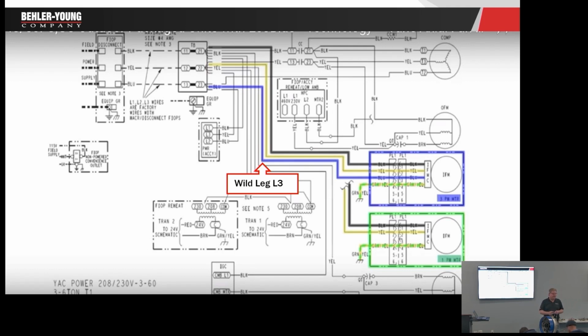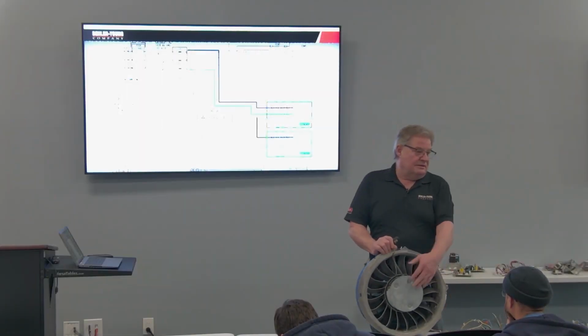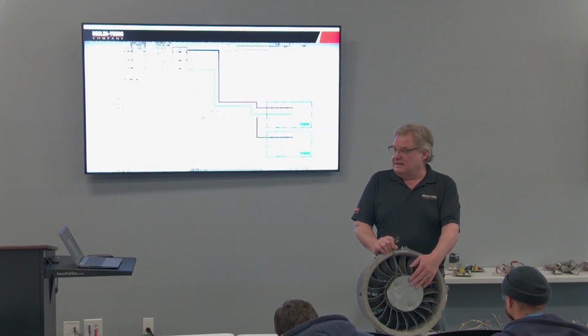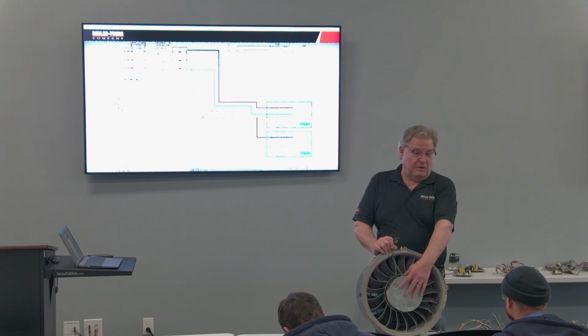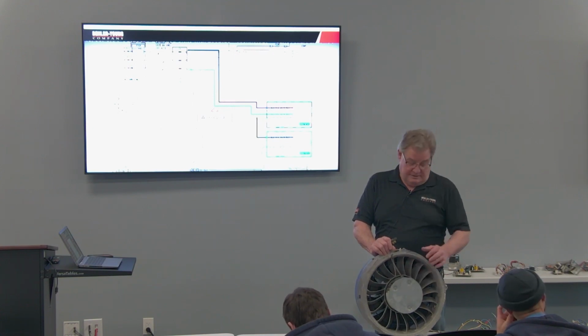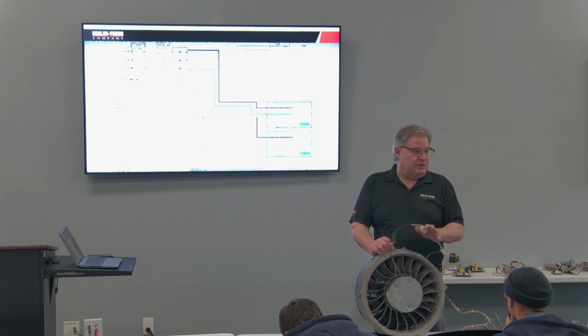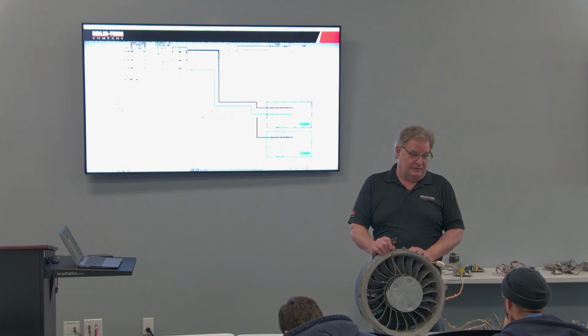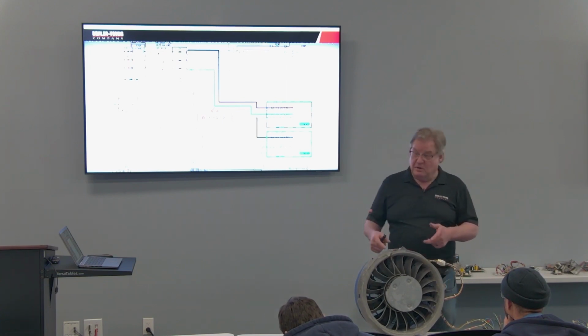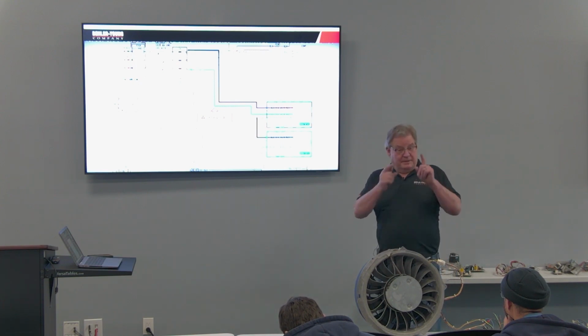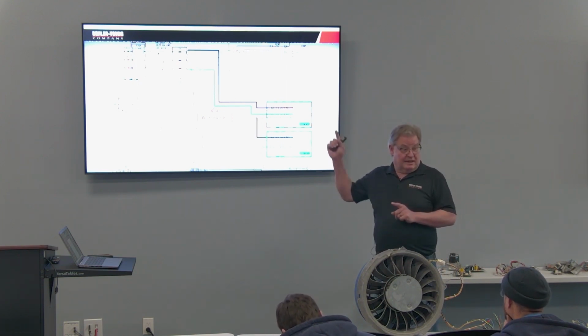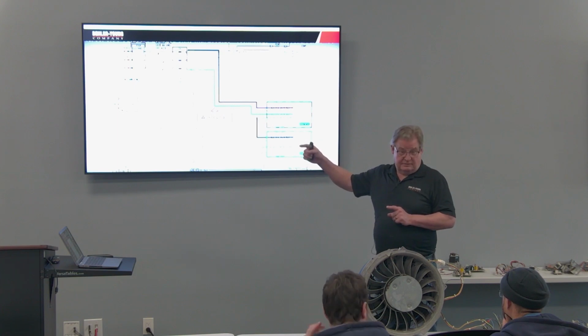First thing we asked is, why do I have to go to blue? Because the first thing that happens when this 230 gets into this motor is it's converted to DC. And then that DC power powers all the electronics in here. They don't want the wild leg going through the electronics, because that could cause this motor to fail. So if you get one of these motors that's been replaced twice, see if you've got a wild leg, and if it's on L2, you want to move it to L3.